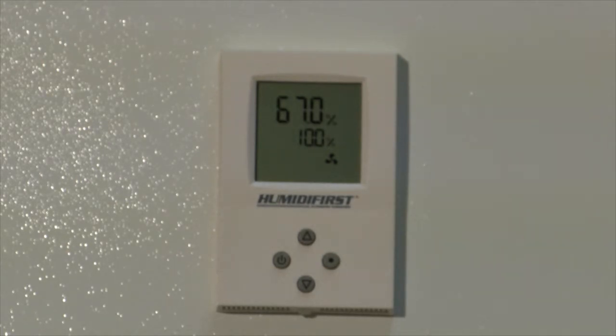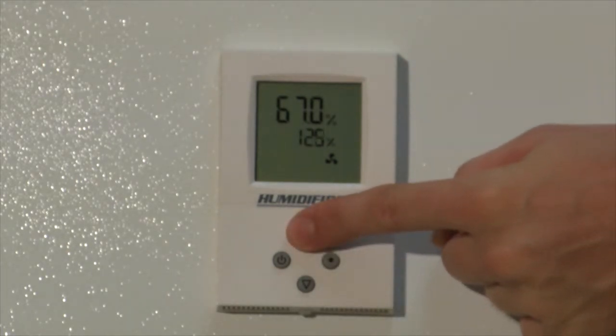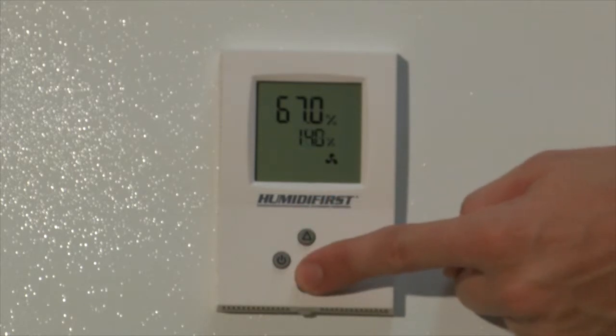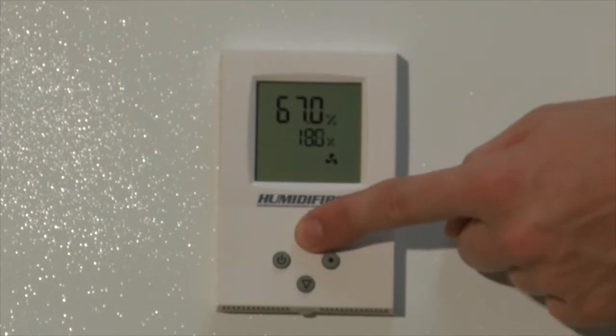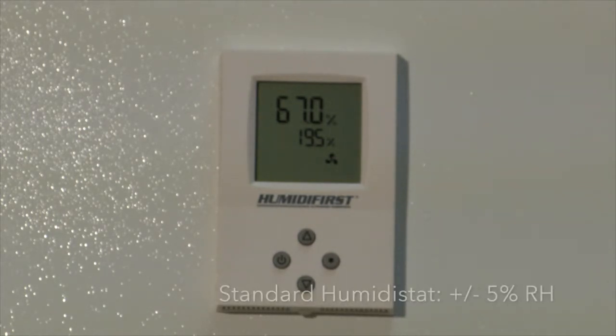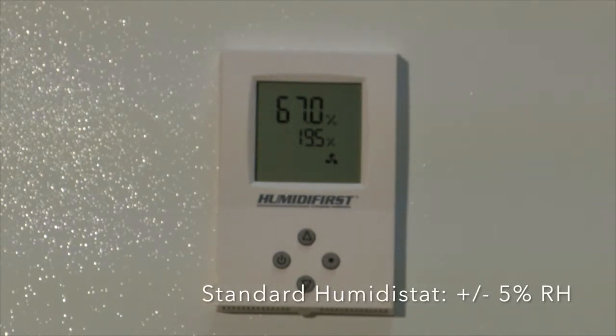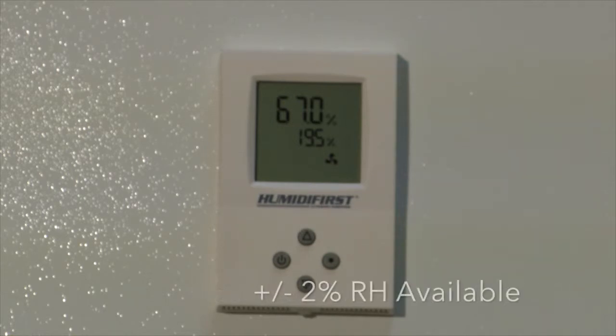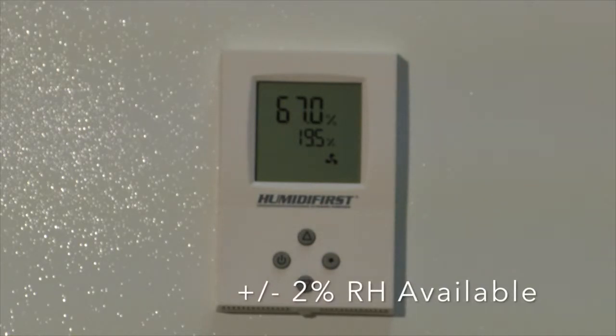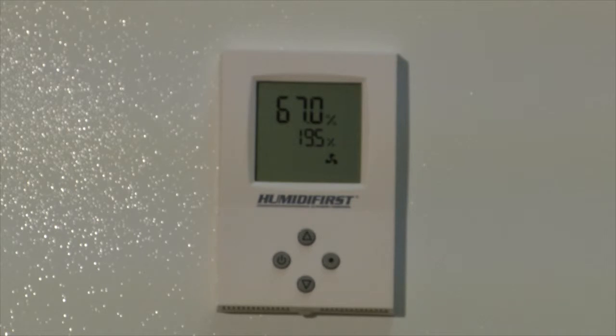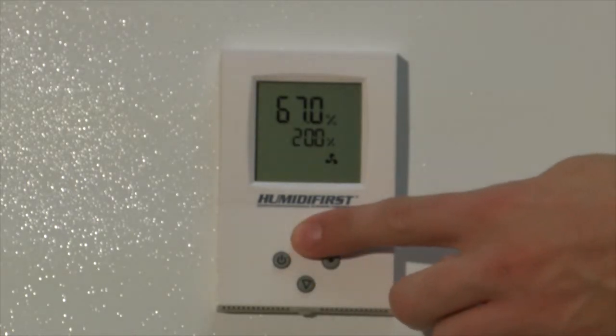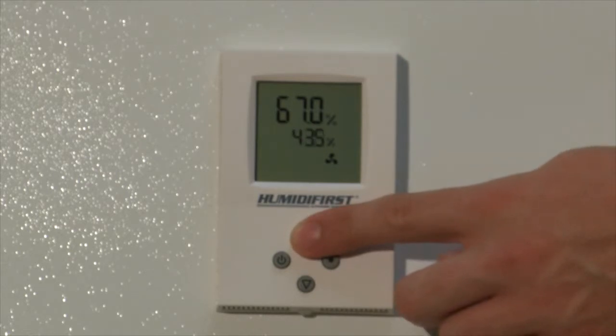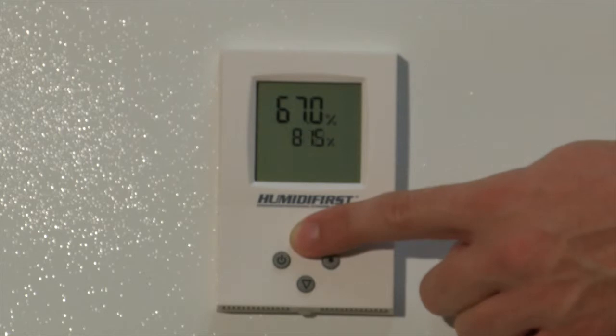To adjust the set point, simply press the up and down arrow to your desired level. The standard digital humidistat has a margin of plus or minus 5%. A plus or minus 2% version is also available. To activate the mist-free humidifier, simply adjust the set point to your desired level above the current relative humidity. In this case, we have a relative humidity of 67%, and we will adjust the set point to 85%.